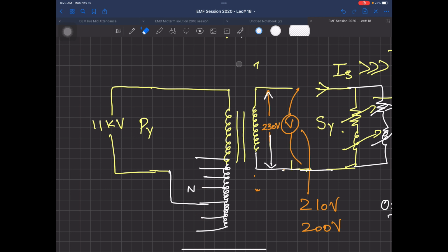This is not a 1-to-1 ratio transformer; it's an 11 kV to 400 volt transformer. I'm speaking in terms of 3-phase, but practically the values differ. So this time you connect to a different tap.